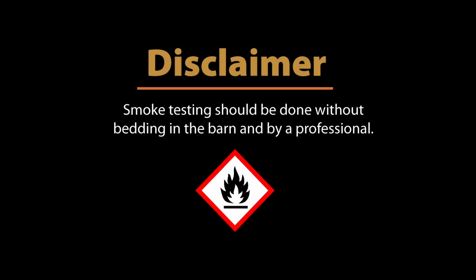out of the building. Today we're in a newer single-story barn, modular inlets on one side of the barn, exhaust fans on the opposite side of the barn with tunnel ventilation for the summer. So we're going to do a smoke test with the minimum ventilation with the current settings in the barn to see if we can identify any issues and help improve the way the air moves through the barn. Smoke testing a barn should be done without bedding in the barn and should be done by a professional.